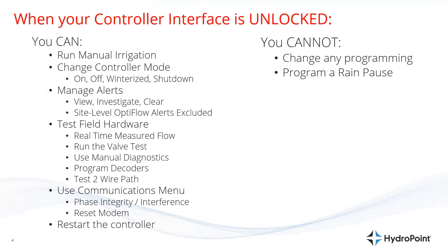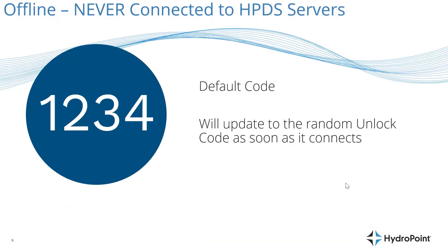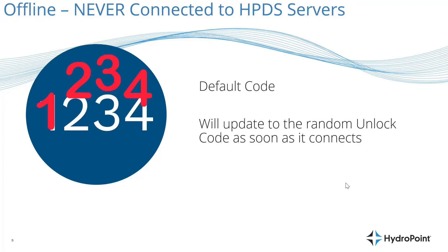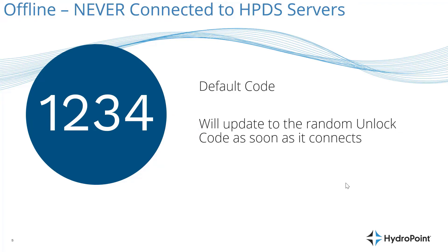At that point, you'll likely go right to the communications menu to diagnose why the controller was offline and how to get it communicating again. One last thing: if your controller has never connected to the HydroPoint servers, it will have a default unlock code of 1, 2, 3, 4. But as soon as the controller connects to the HydroPoint servers, that unlock code will update and you'll have to find it at WeatherTRAK Mobile or WeatherTRAK.net.